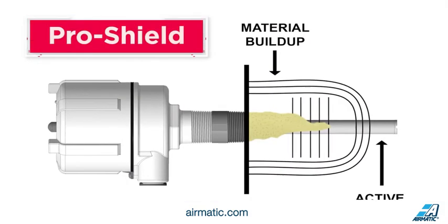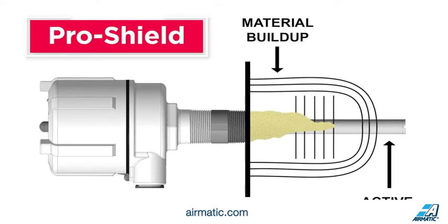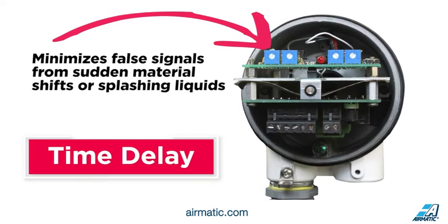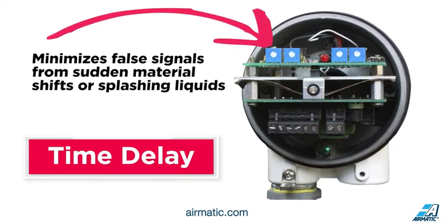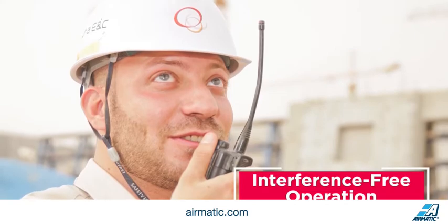Pro-Shield protects against false readings due to buildup on the probe or bridging between the sidewall and the probe, allowing the probe to be used in dusty, sticky, or clingy materials. The time delay feature minimizes false signals from sudden material shifts or splashing liquids — users simply set a time delay of up to 30 seconds before alerting to a signal change. Pro-Shield probes are immune to RF signals, ensuring interference-free operation from electronic plant equipment or two-way radios.